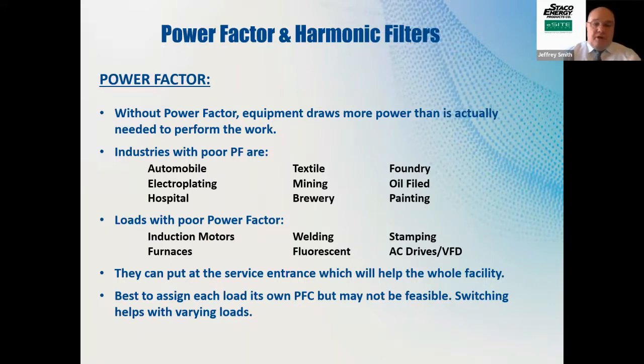Poor power factor industries: automobile manufacturing, electroplating, hospitals, textile, mining, brewery, foundry, oil field. These are the types of things: induction motors, furnaces, welding, fluorescent lighting, stamping, AC drives, VFDs. These are also cases where the power factor can be low enough that if you put in power factor correction, you can increase the benefit you get back from it. All right. Next slide, please.